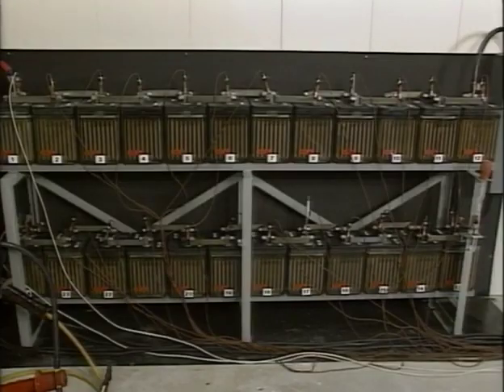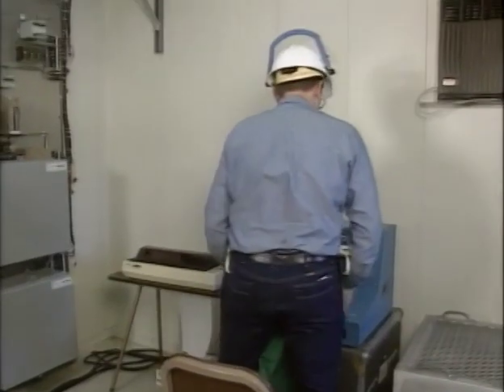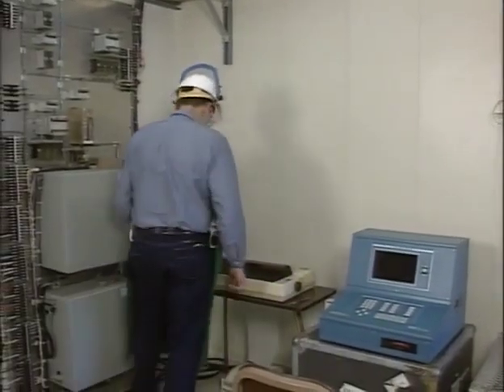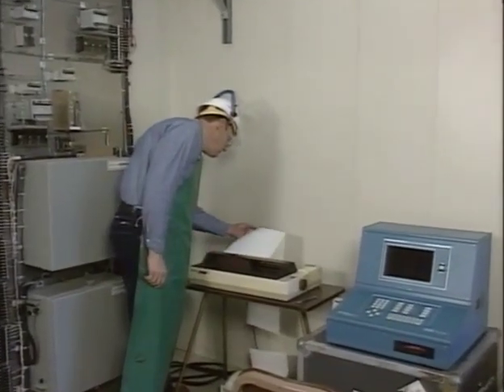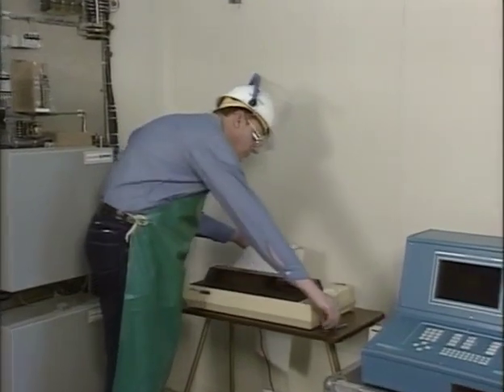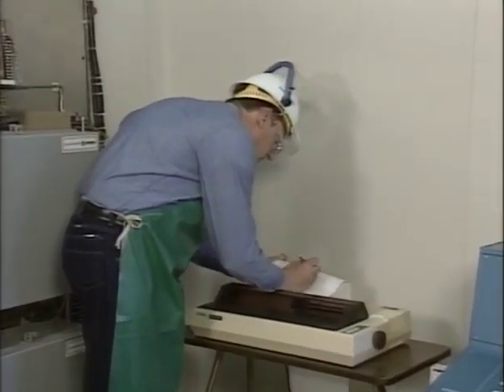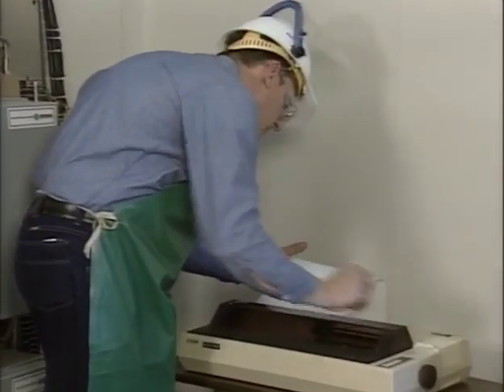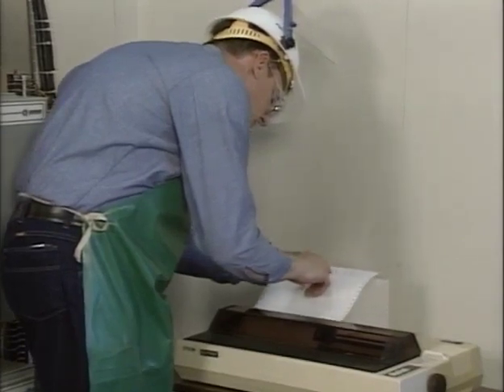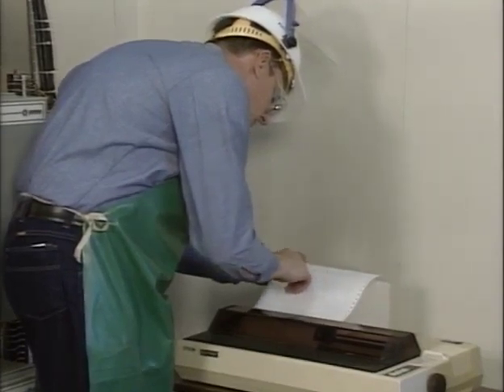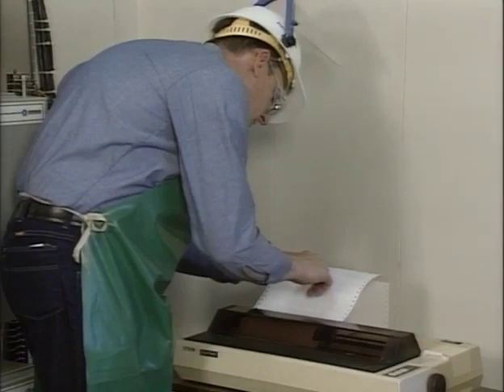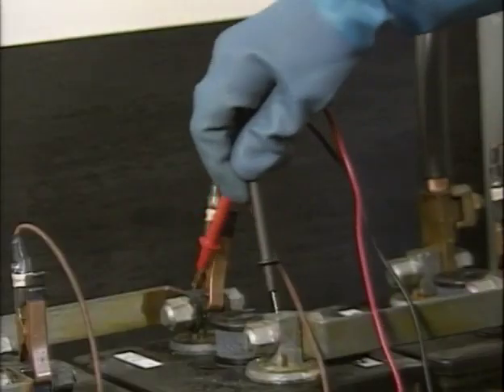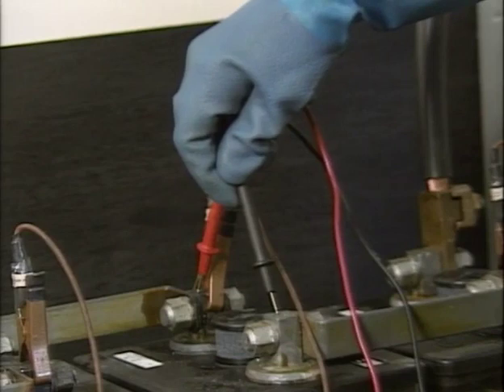During the integrity test, a high current is drawn from the battery. This is a critical part of the test. Individual cell voltages must be read and compared against each other. If a cell voltage is 0.03 volts below the average or adjacent cell voltages, the cell should be checked with a digital voltmeter to determine if the excessive voltage drop is caused by the cell or by the intercell connector. Cell voltage is measured across the positive and negative terminals of the cell to exclude the intercell connector.